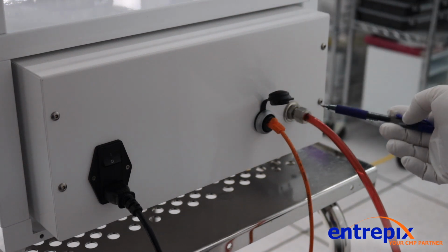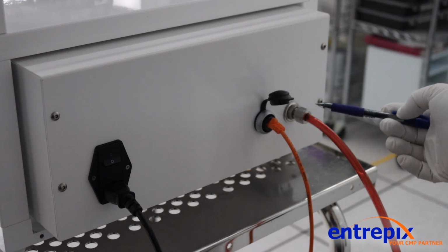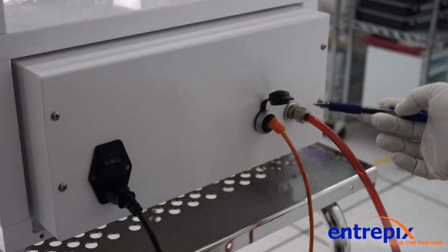The last connection is for incoming gas. We recommend using N2, but CDA is also acceptable. The recommended incoming pressure is 90 psi, and it will operate anywhere between 70 and 150.